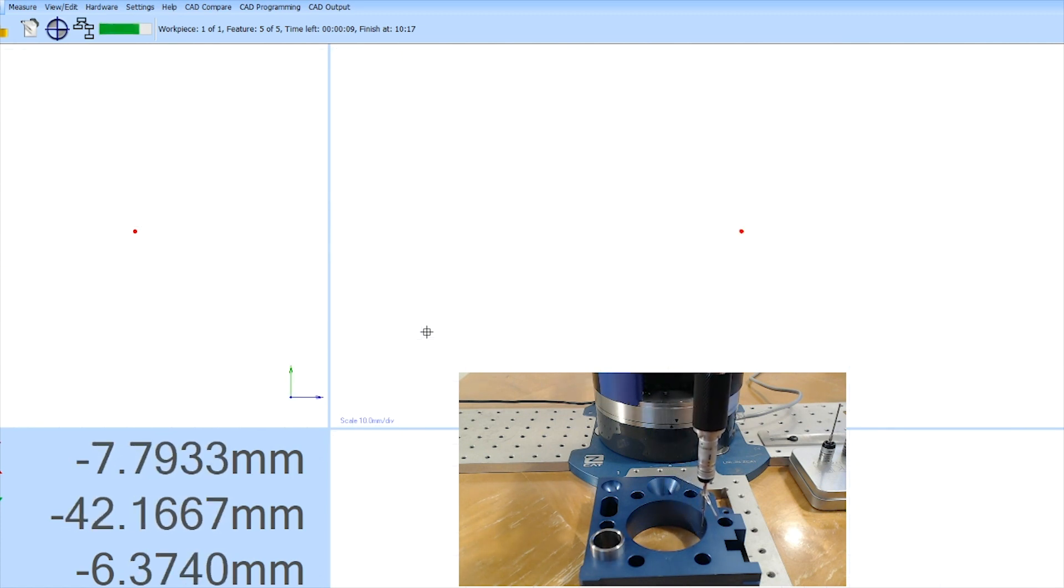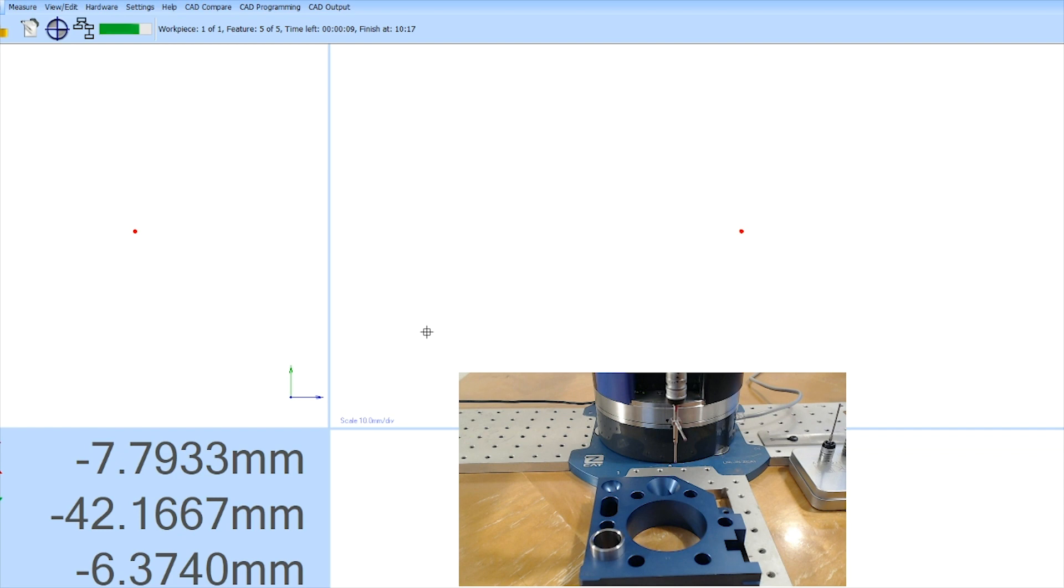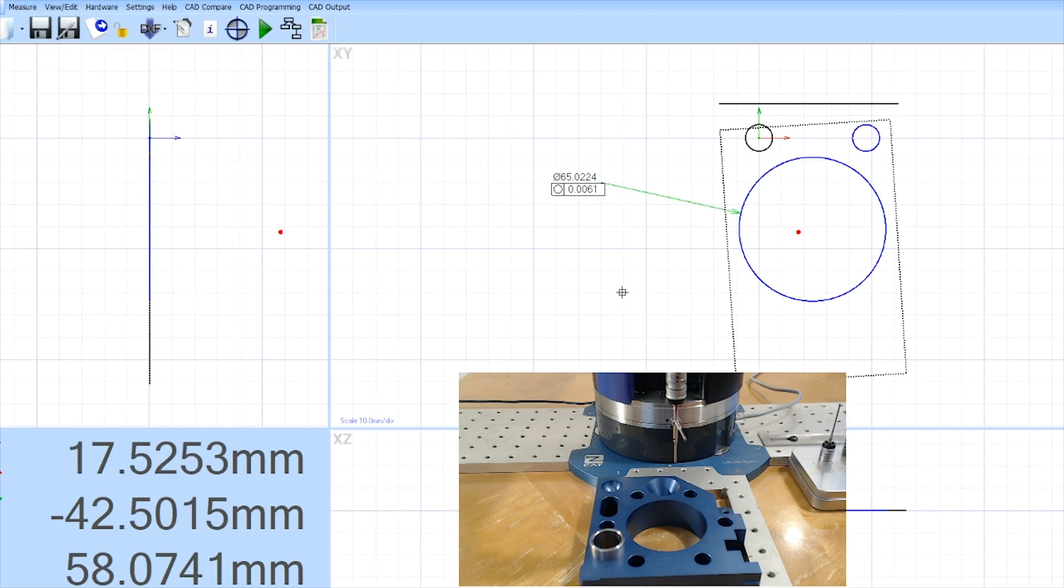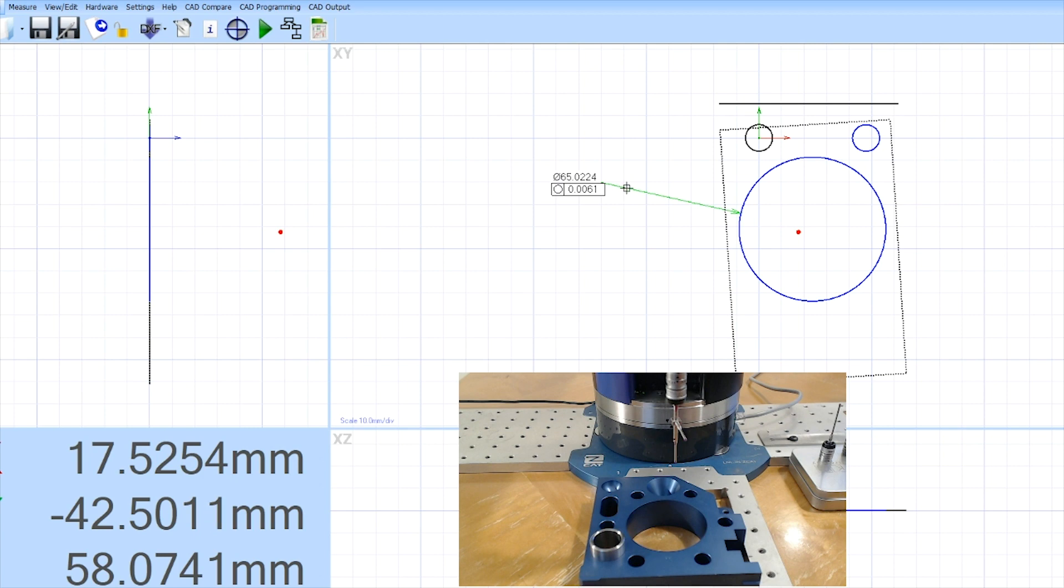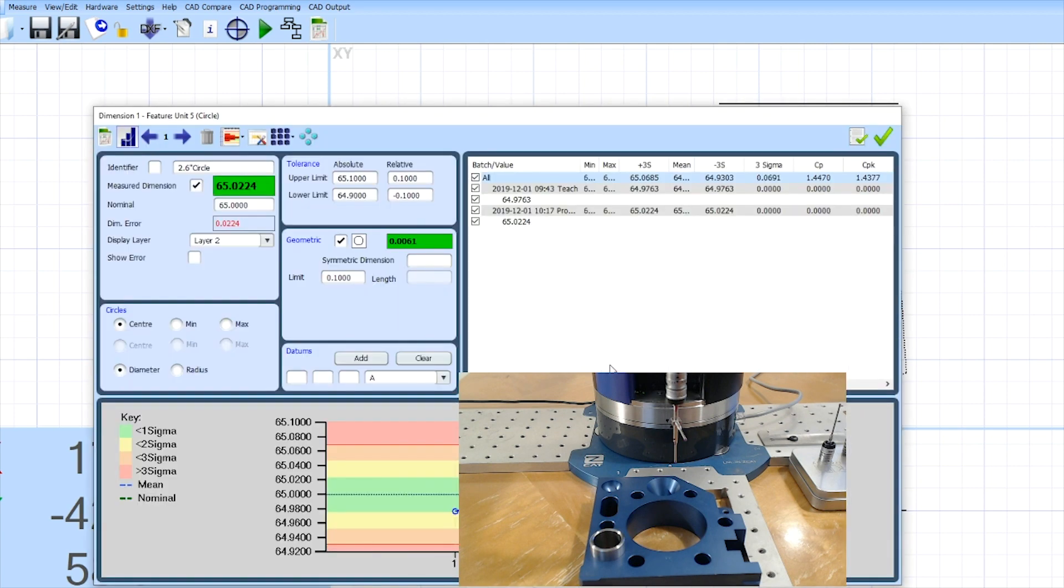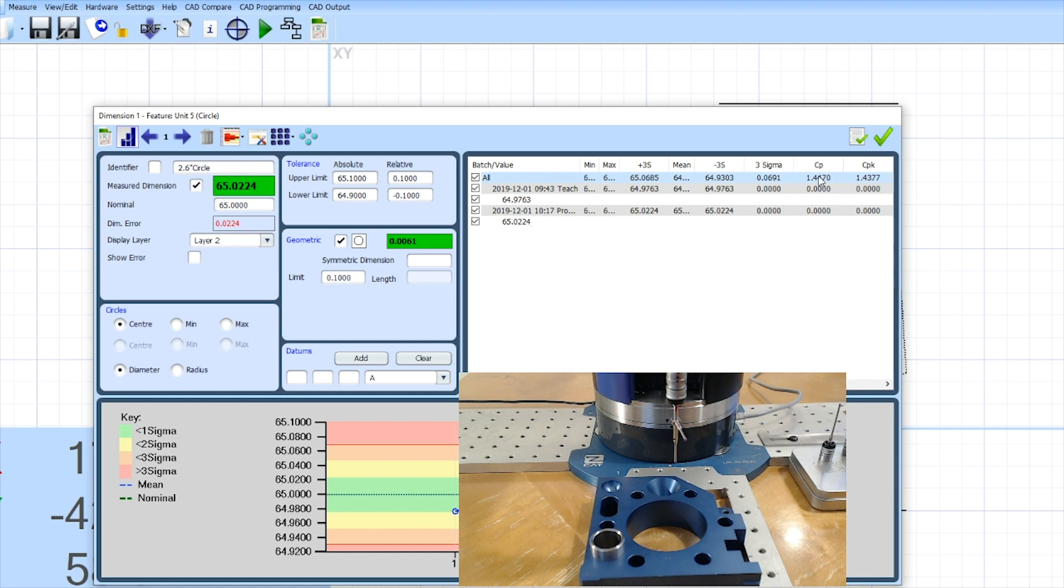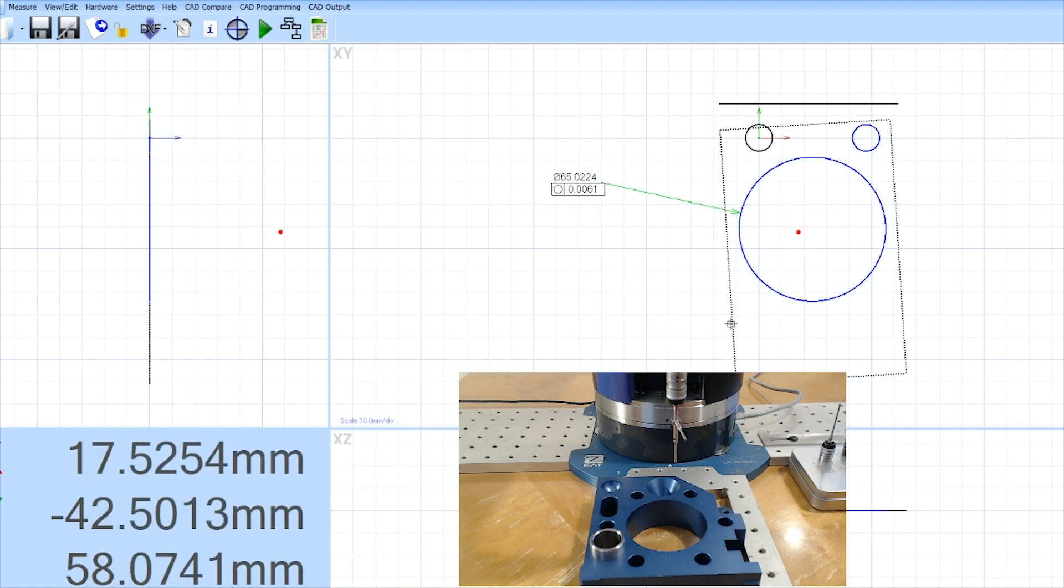it will update that automatically and you'll see it updated that at 65.022 and a six micron roundness. If I look back at what I measured the first time it was 64.9763. So quite a bit of difference. That's just a good demonstration of the difference between manual and direct computer control.